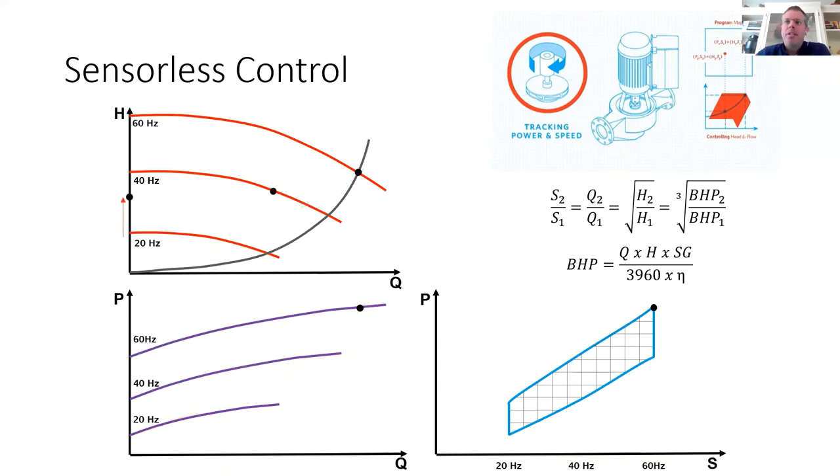Additionally, if you have to make adjustments out in the field, if the minimum head required needs to be adjusted, we can program a new minimum head set point into the controller and it's going to draw a new quadratic control curve for the on-site conditions.